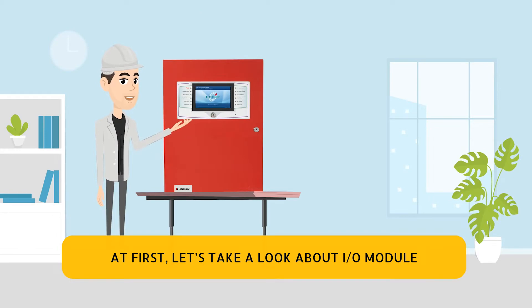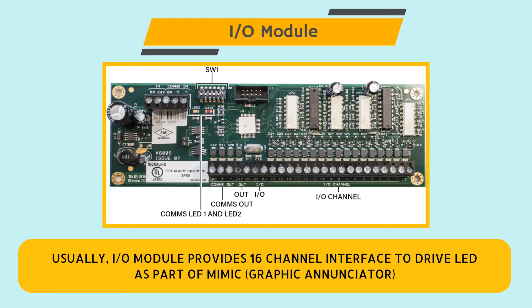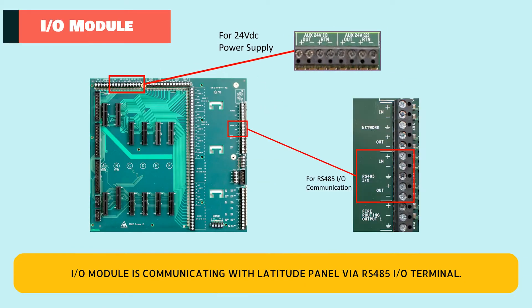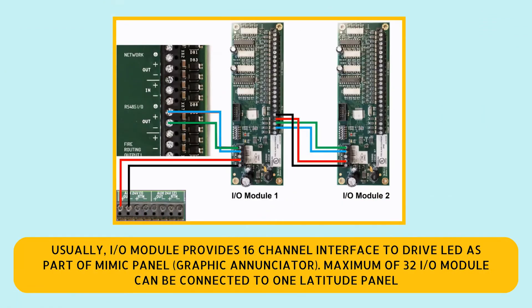First, let's look at the I.O. module. The I.O. module provides a 16-channel interface to drive LEDs as part of a Mimic Panel or Graphic Annunciator. The I.O. module communicates with the Latitude Panel via the RS-485 I.O. terminal. A maximum of 32 I.O. modules can be connected to one Latitude Panel.